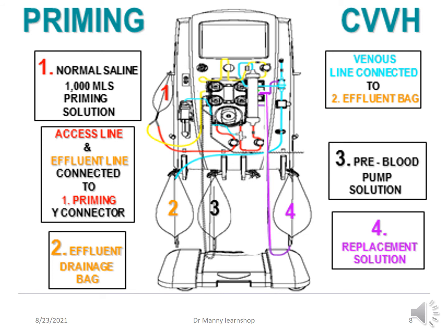This will prime the access line and the effluent line because they're connected to the priming Y connector, which we'll be reviewing when we look at adjuncts in Learnshop 6. It's connected to the effluent bag, which it drains into, number 2. The pre-blood pump solution 3 is connected, and the venous line is connected to the effluent bag, and the replacement solution replaces or primes that line as well, which also drains into the effluent bag.